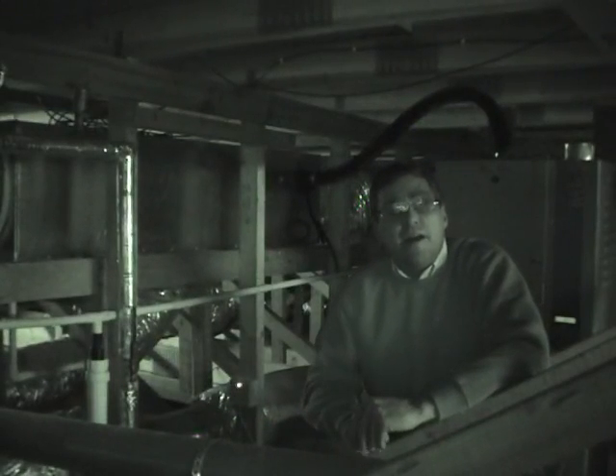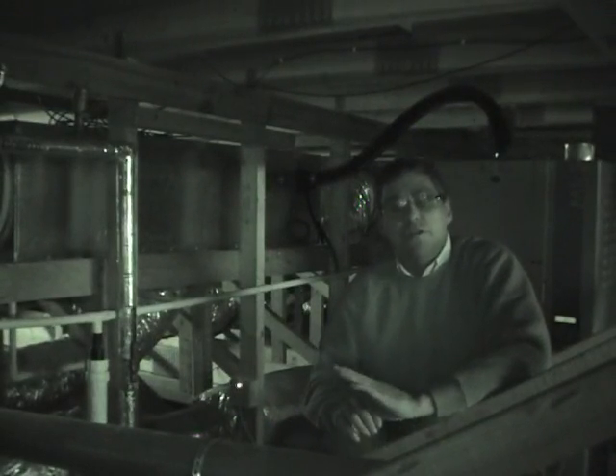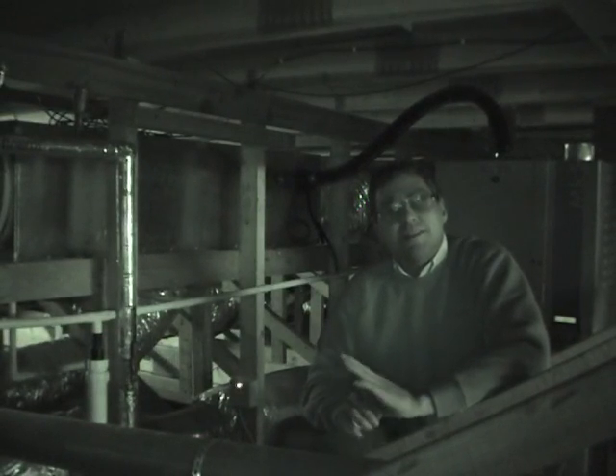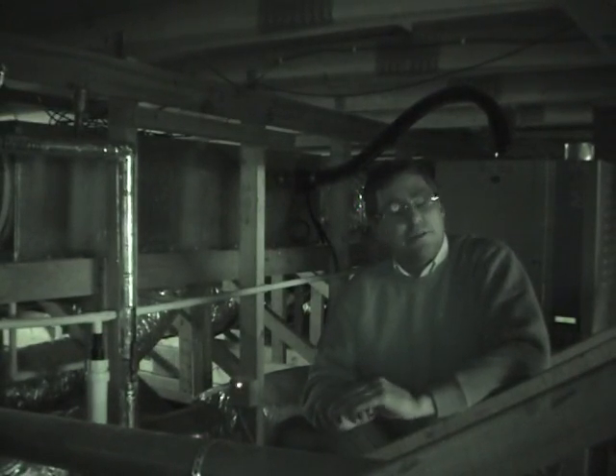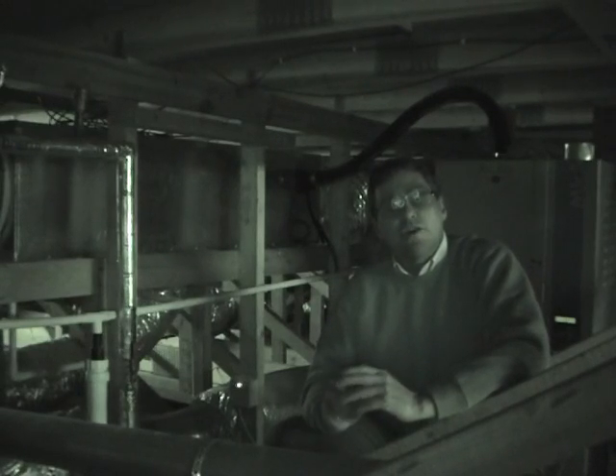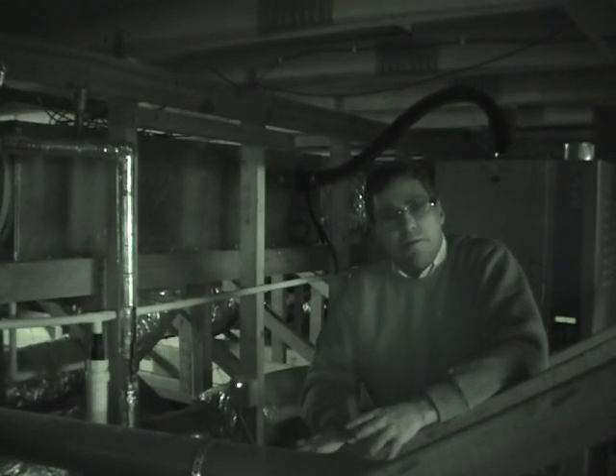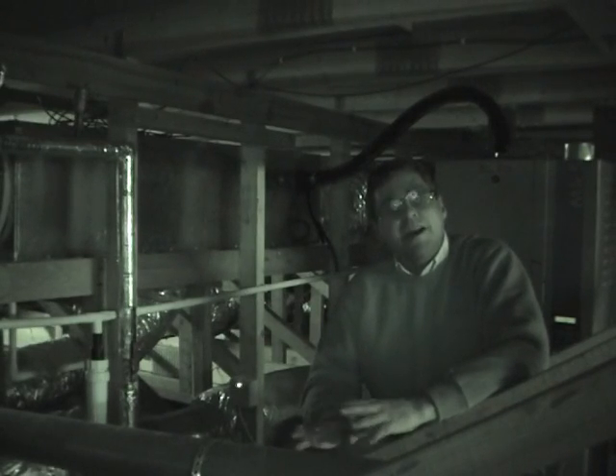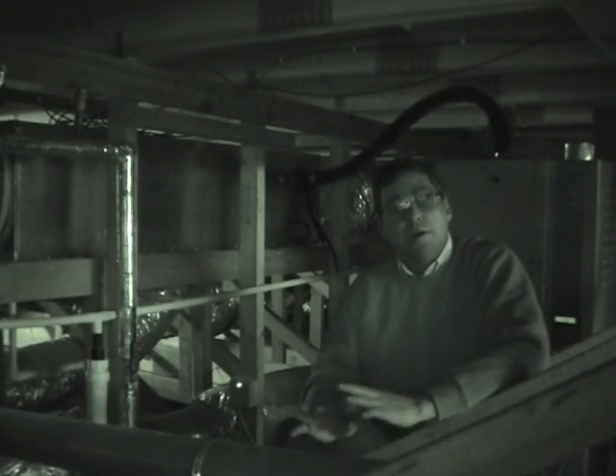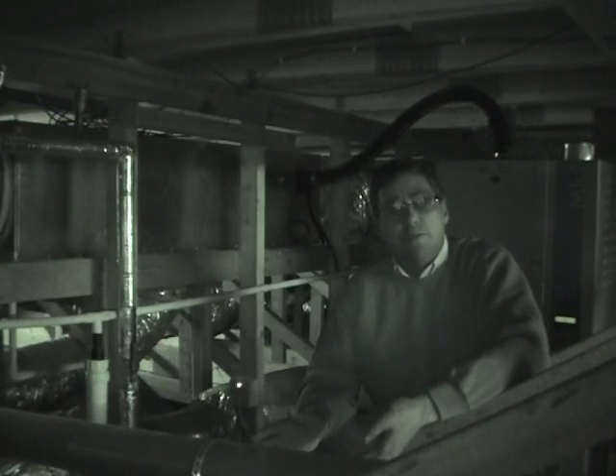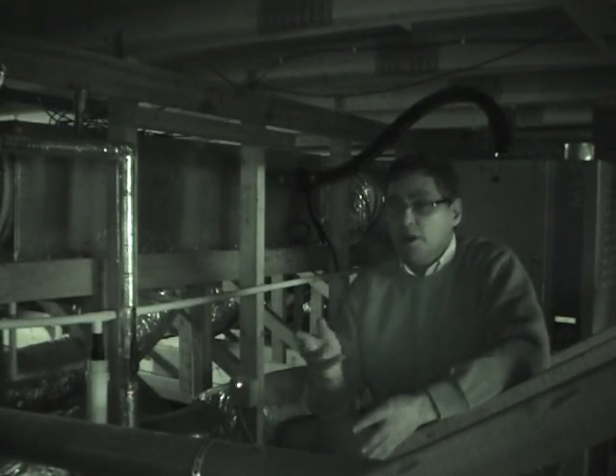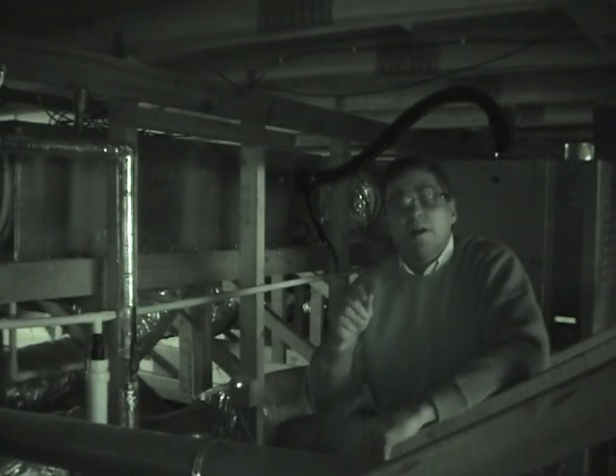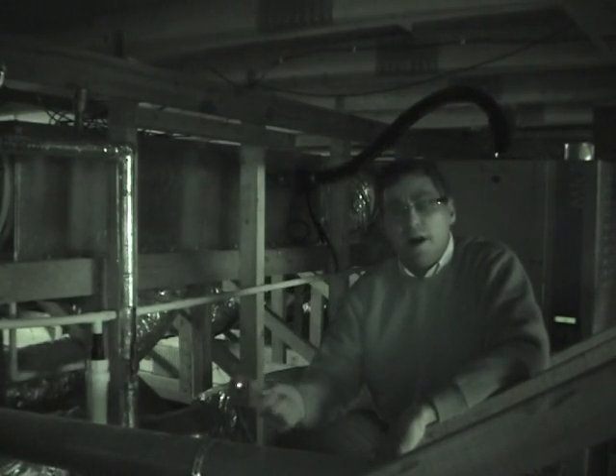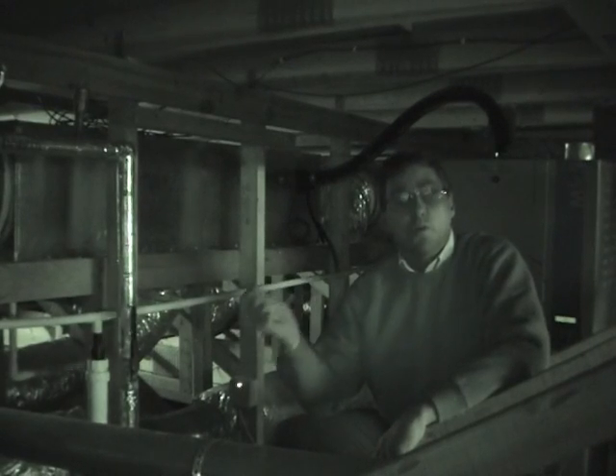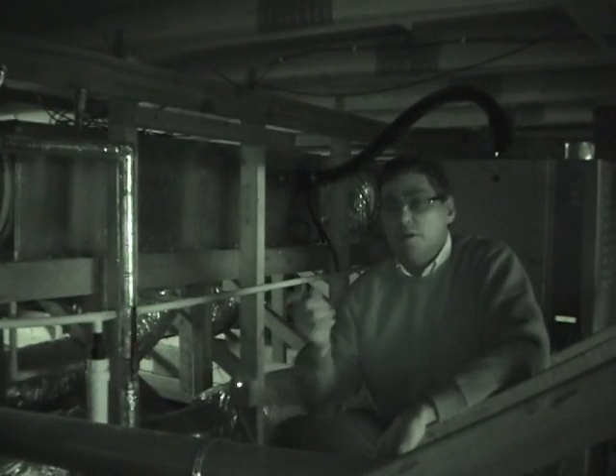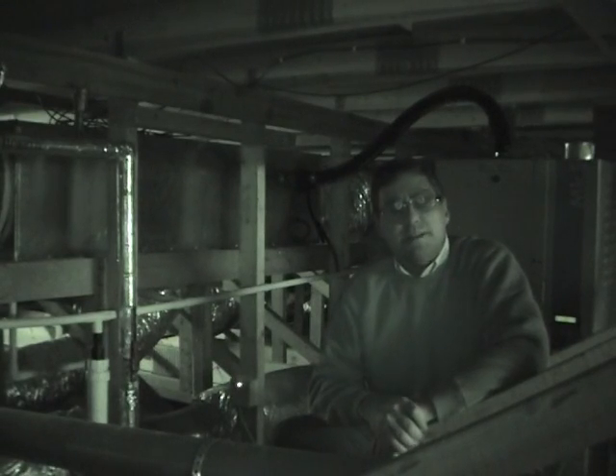Lastly, over to the left there is the cooling coil—our comfort cooling coil. It's attached to the inlet ducts that supply all the living areas, and we get the coolant from the ground pipes connected to the heat pump. So we have an abundance of free coolant available simply by switching the circulation pump on, running fluid from the ground up through our cooling coil. We can cool the whole house down for the cost of running a circulation pump, about 5 pence a day.